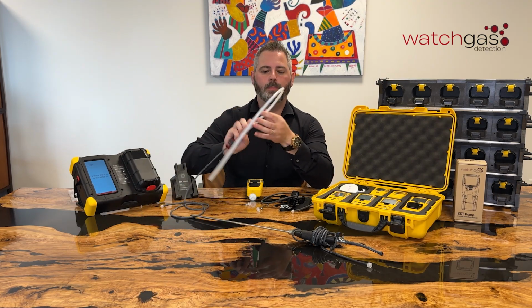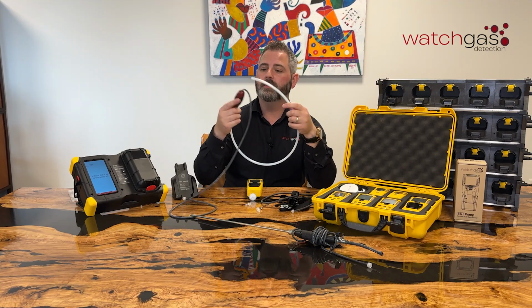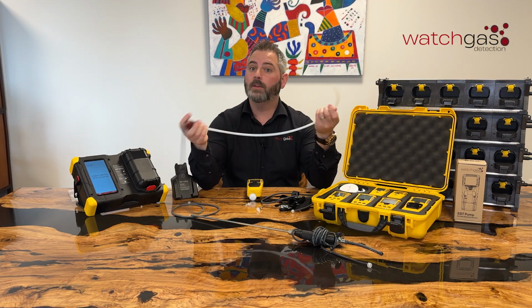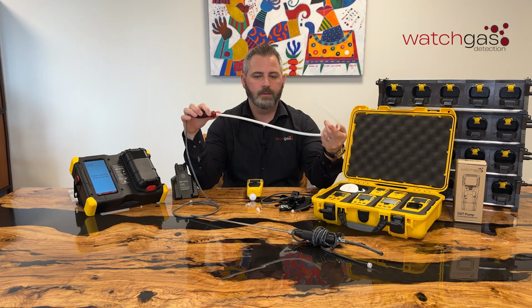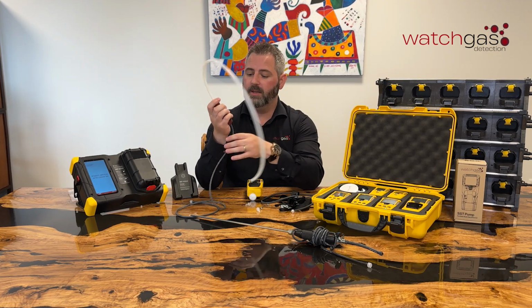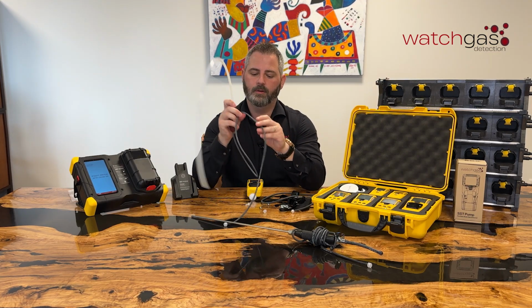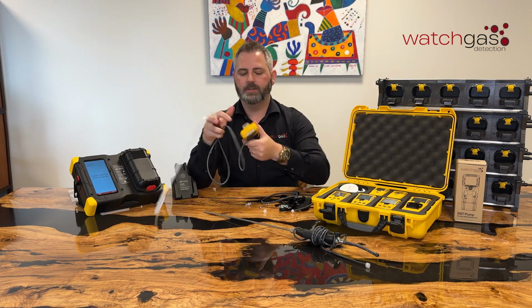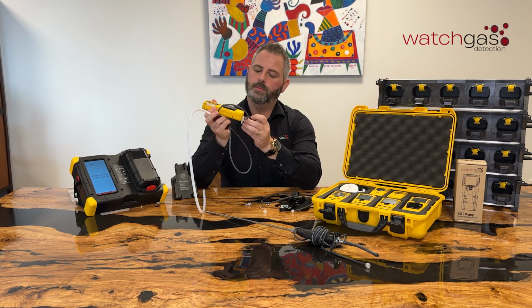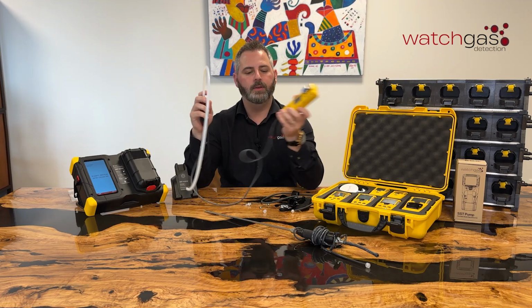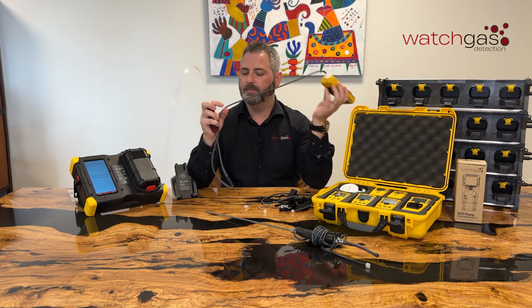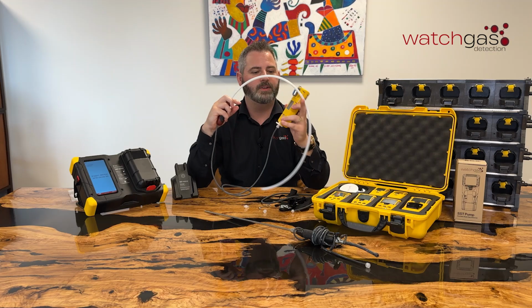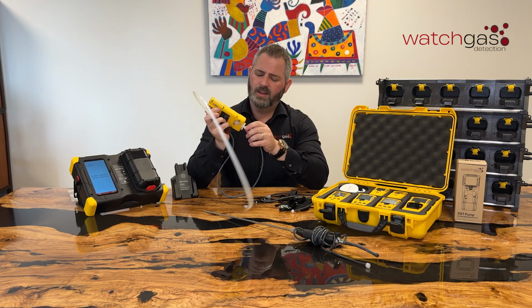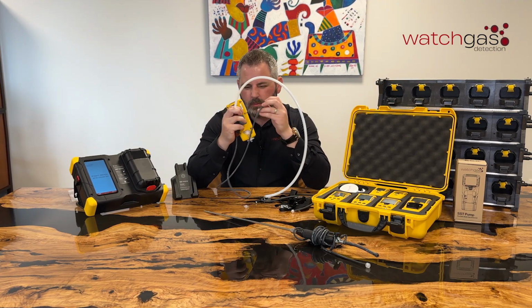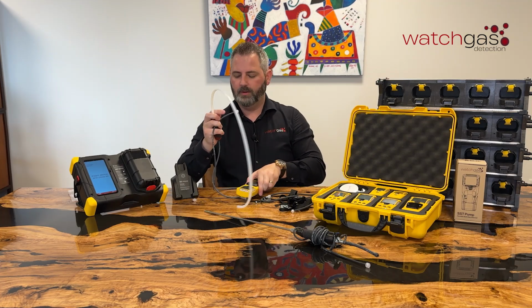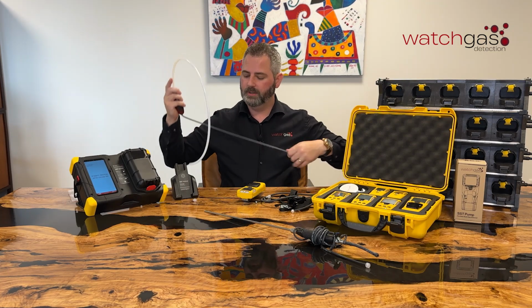This is a mailbox probe, one of our cheapest probes. It's Teflon tubing that can be fed into a tight environment or even through a mailbox, as the name explains. On the end of that you have your luer-lock tubing, which attaches onto your pump, so you can take readings like so. You can see the high level of flexibility the luer-lock tubing has compared to the Teflon tubing - both give you the same low level of absorption rate, giving a high level of reliability when testing.